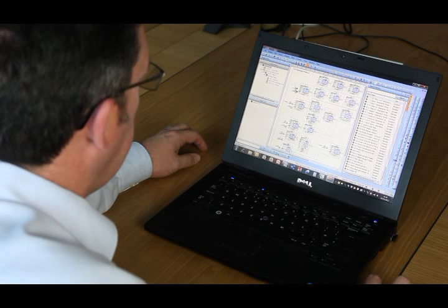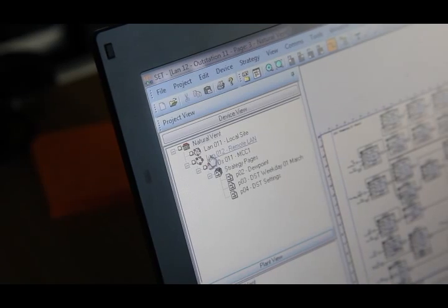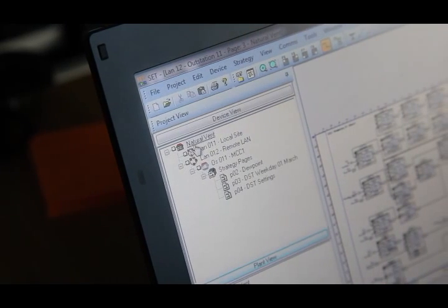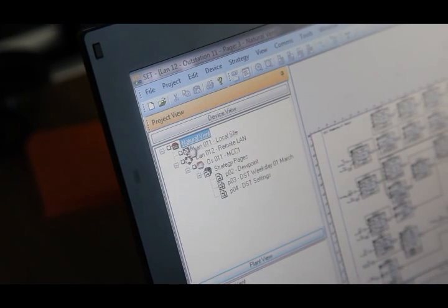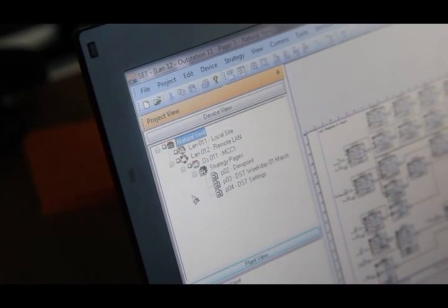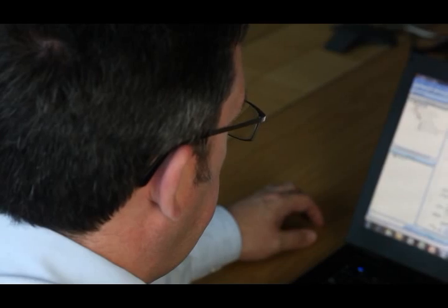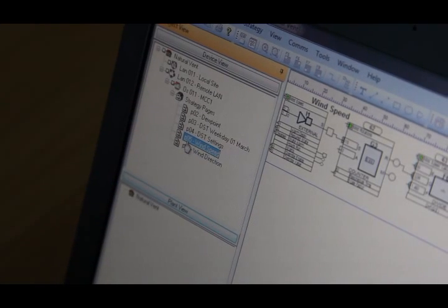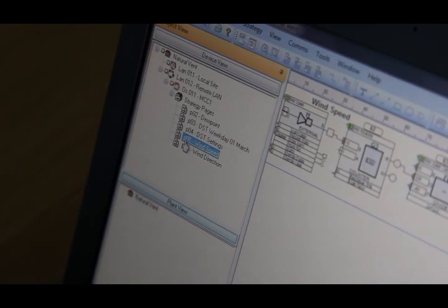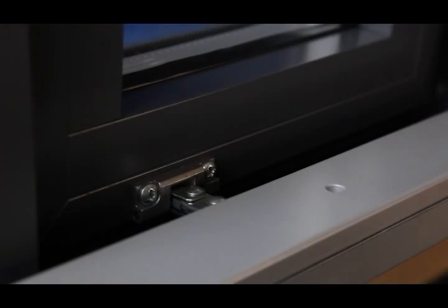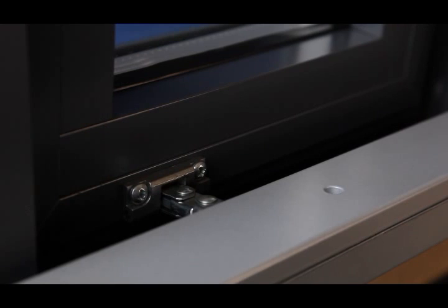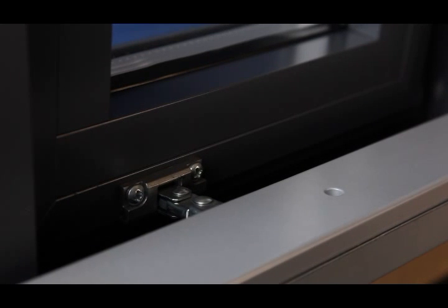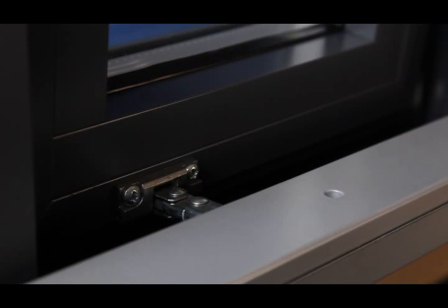All of the control logic deciding when and by how much the window will open will be custom programmed within the IQ3xcite or IQ Eco controller. The TREND IQ controller will send commands to the NVMC units to drive the window actuators to the desired positions.